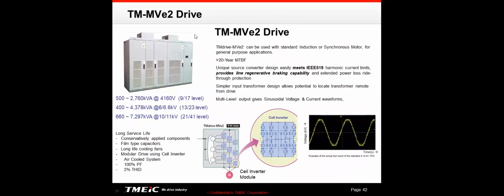This is a TMEIC MVe2. It's an active front-end drive. You'll notice that it is 9 levels for the 4160 volt version, 13 levels for the 6600 volt version, and 21 levels when you get to 10 or 11 kV. So 9 levels from 0 to peak, 17 levels from peak to peak. And if you look at that, man, that's a sine wave. It also has 100% power factor, as we talked about, and 2% total harmonic distortion.